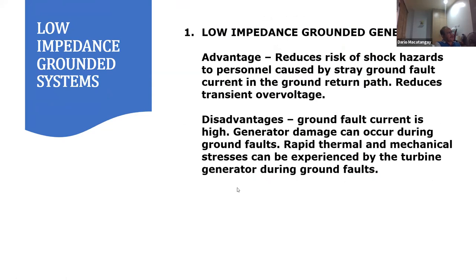The next type of system is a low impedance grounded generator. The advantage of this is that it reduces the risk of shock hazards to personnel caused by stray ground fault current in the ground return path, and it also reduces the transient overvoltage.